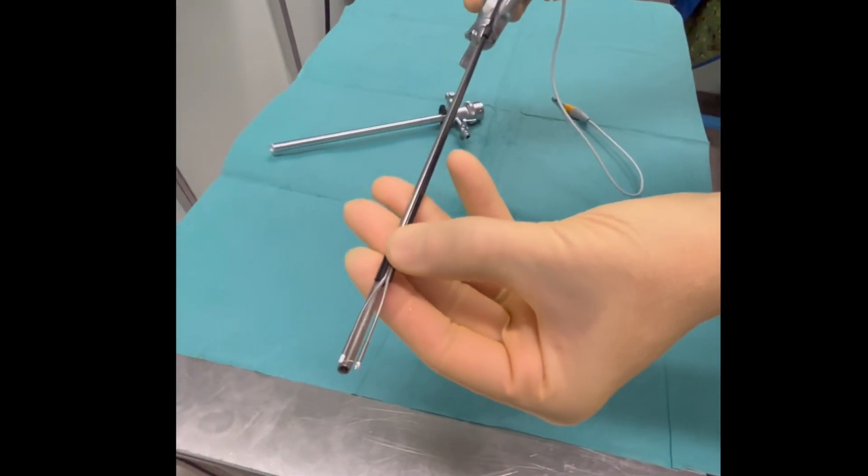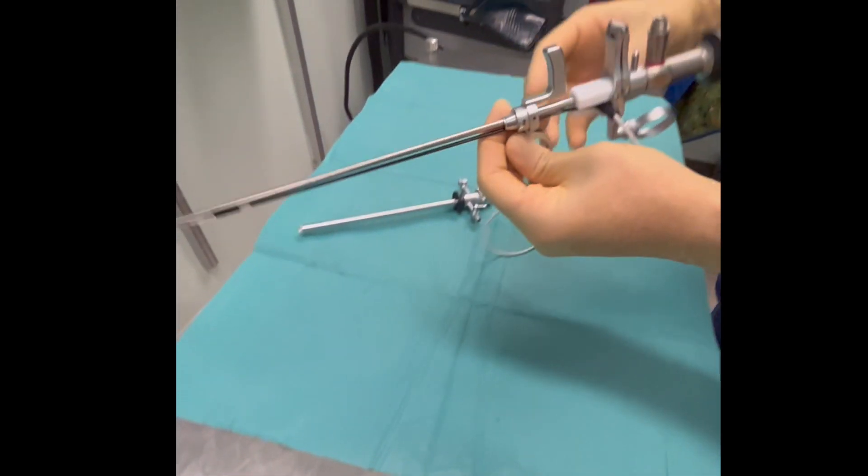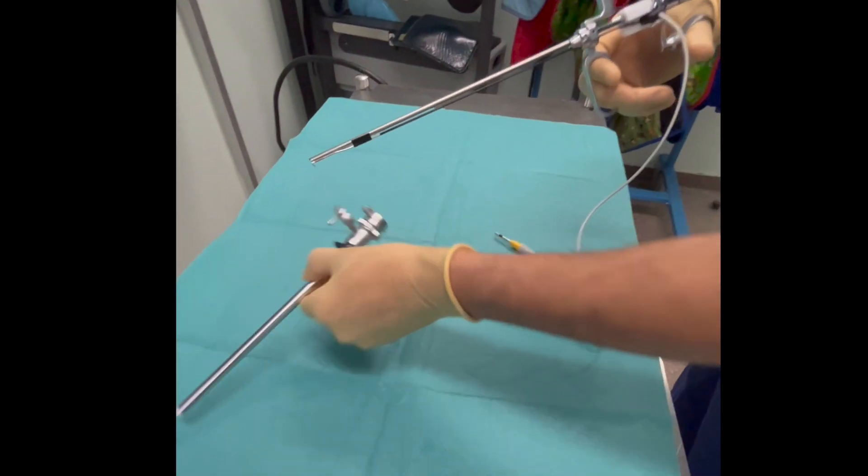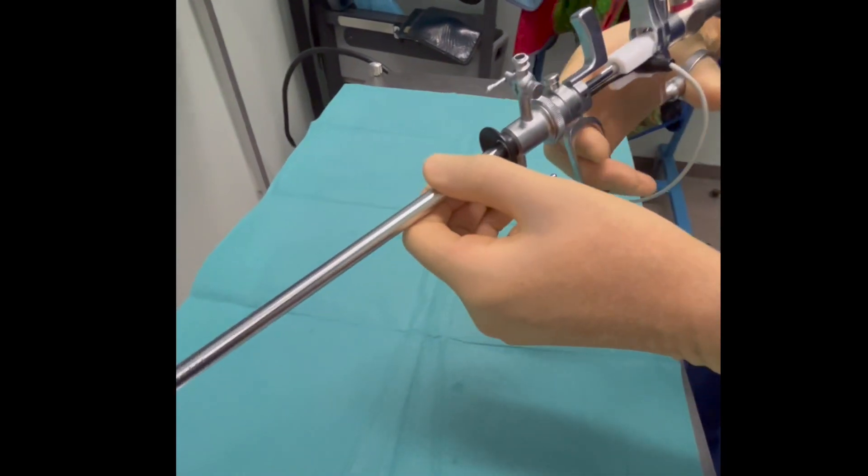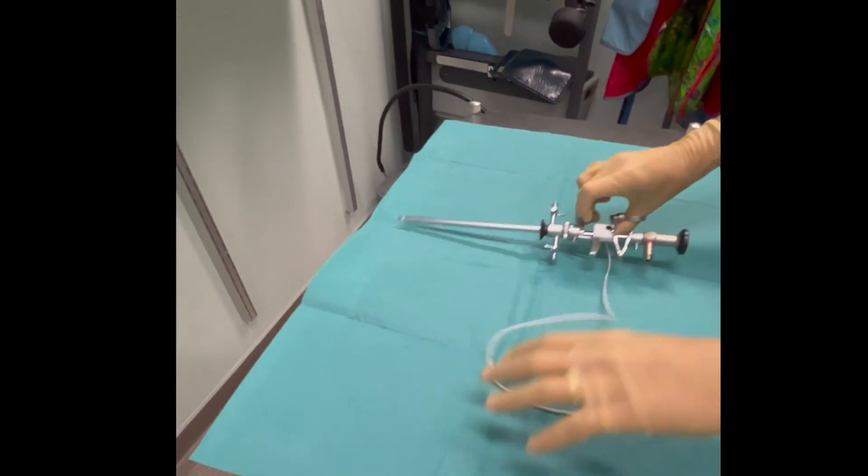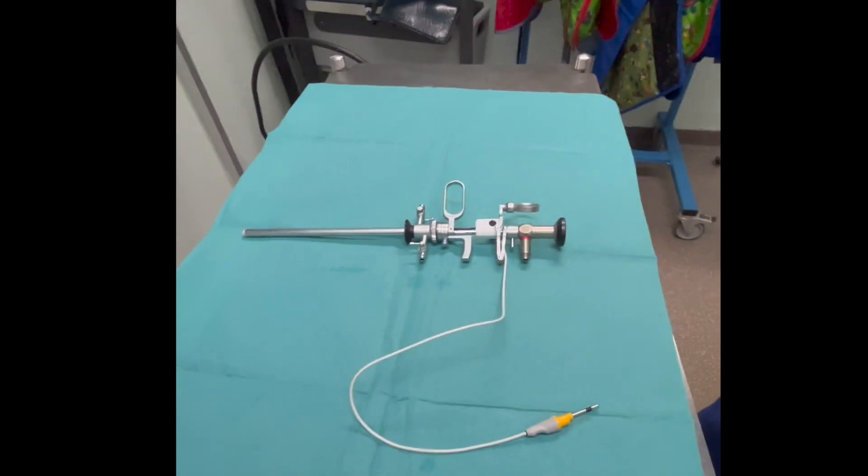The distal end is then fixed to the telescope. The black knob should fit into the system and is key to prevent any water leakage. This is the final assembly of the resectoscope. Thank you for watching.